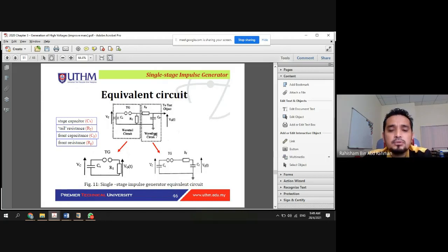Say we want to produce an impulse output at 100 kV, and the charging capacitor, the stage capacitor, if charged fully, could produce up to 200 kV. There will be a certain preset clearance distance between the two electrodes, in case we want this capacitor to discharge at 100 kV. So the trigger gap needs to be adjusted to a certain distance, making them closer, so that at the high stress level there will be a discharge between the two, an air breakdown, so that the circuit will conduct and trigger the impulse.